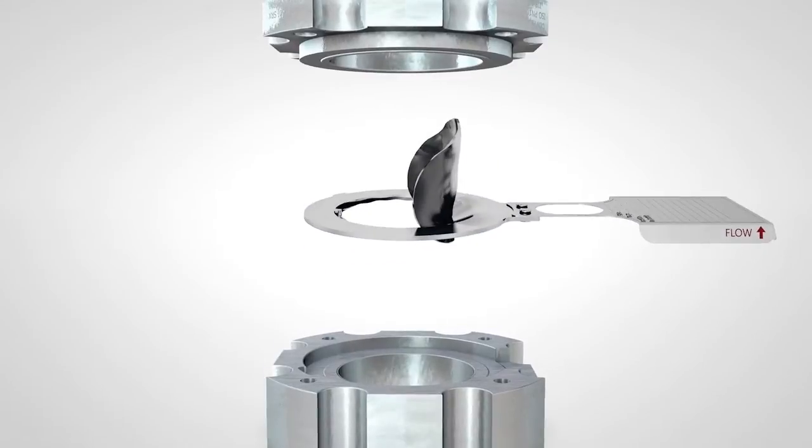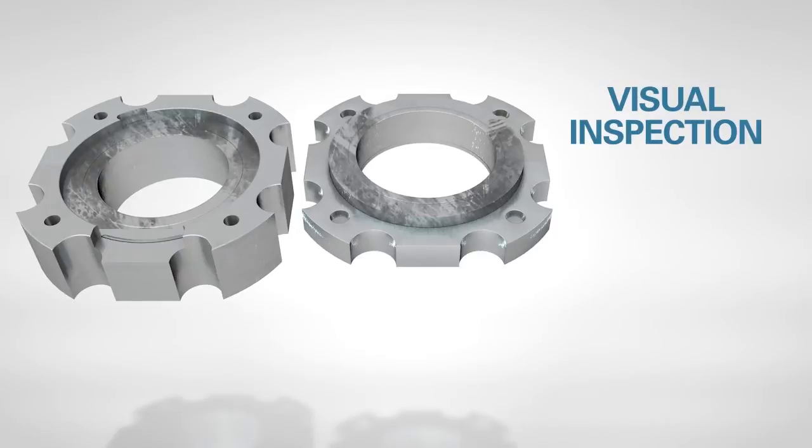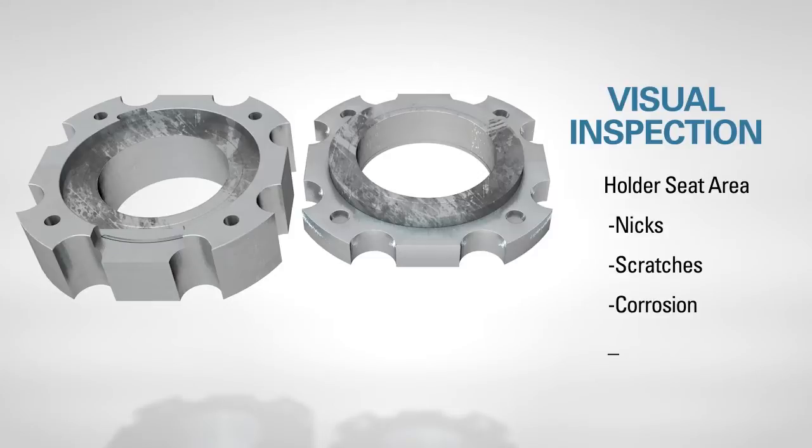If this is an existing installation, do a visual inspection of the rupture disc holder. Inspect the holder seat area for nicks, scratches, corrosion, or deposits left by the process media.